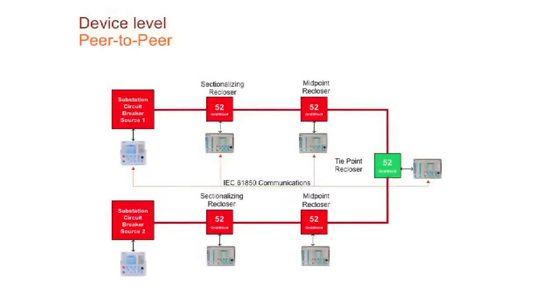Once this receives the lockout message, if you can go to the next slide, it opens up automatically because it knows the fault. If my upstream recloser received a permanent fault and went to lockout, it means that there's a fault upstream. So I'm not going to reclose into it. I'm just going to go ahead and open. And this one receives the lockout message from the sectionalizing recloser, which detected a fault, and receives another Goose message with the breaker status from the midpoint recloser. Because it basically is waiting: okay, I had a fault upstream, so I lost my main source. But I don't want to close it until I'm sure I've isolated the fault. So once it receives this breaker status via Goose message on the communication network, it closes and isolates the fault.